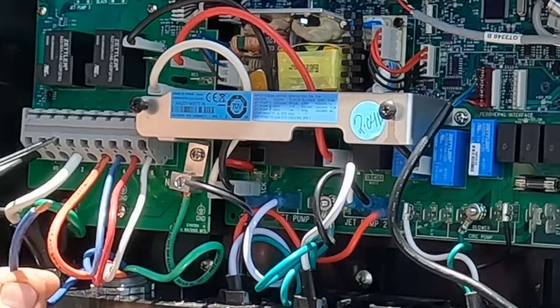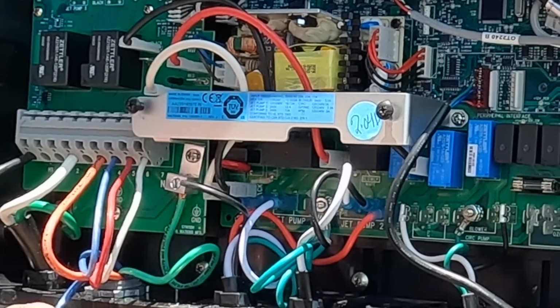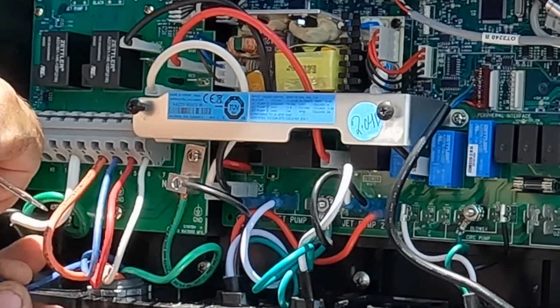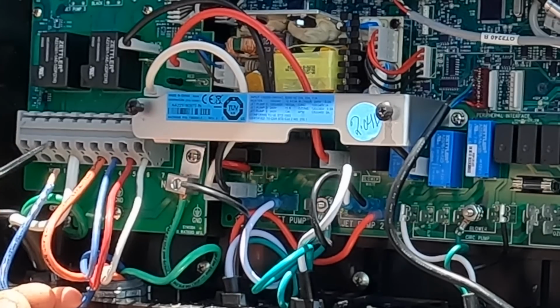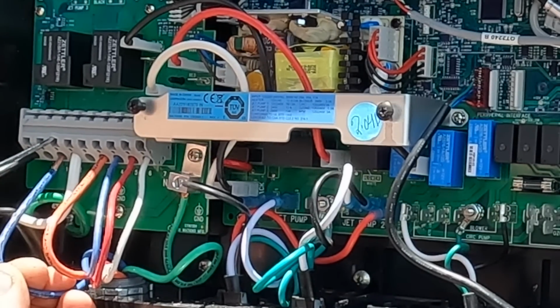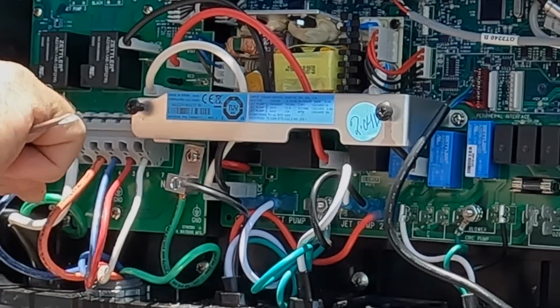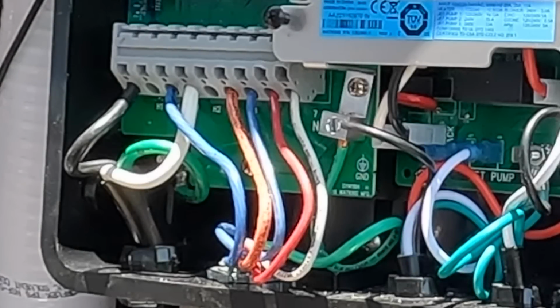So as you can see, I stick my screwdriver in there and I push up on the screwdriver so it pushes the spring clip down, which allows the wire to be connected in the terminals here. Not exactly my favorite thing. So there you have it. So I got a 20 amp 240 volt circuit, a 30 amp 240 volt circuit, a neutral that's connected to the 20 amp circuit, and I got a number 10 equipment ground there all the way on the right. That's how the wiring sits inside the control panel.